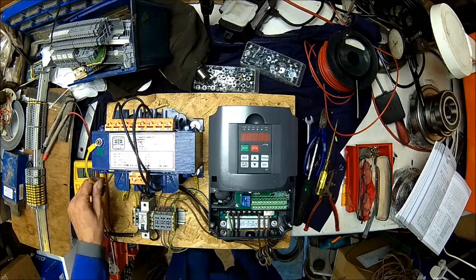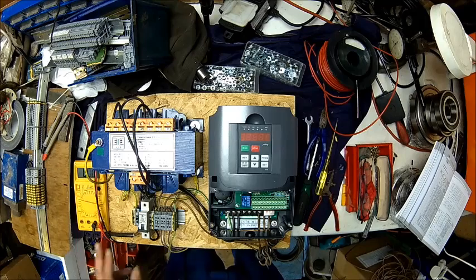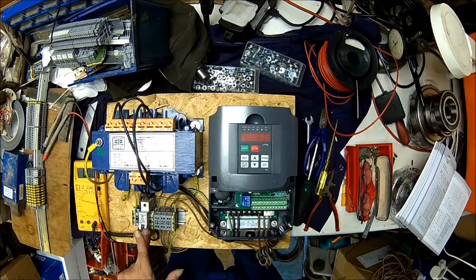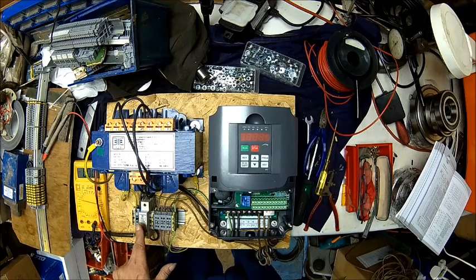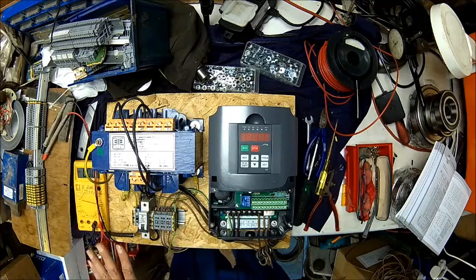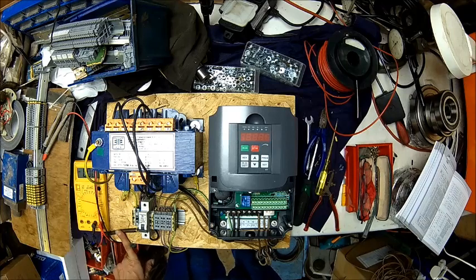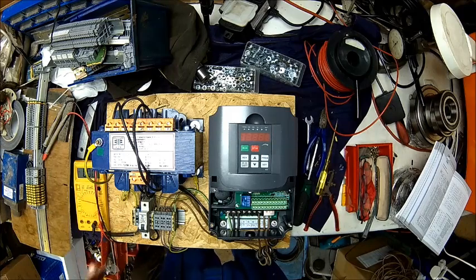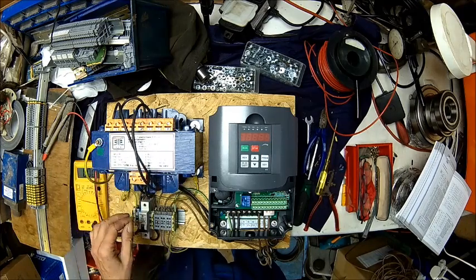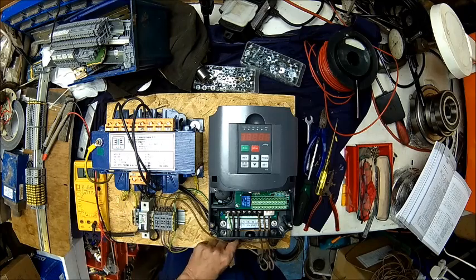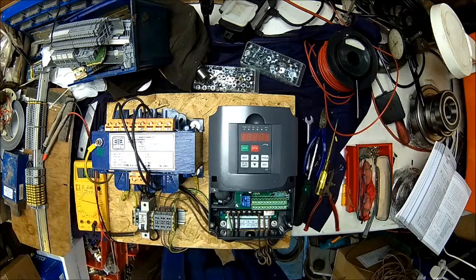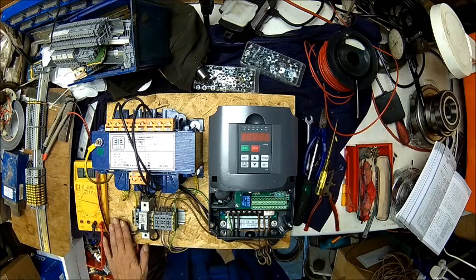Alright, everything is grounded. Inverter is grounded, transformer is grounded. The breaker is the maximum rating of the inverter, plus a little bit of inrush current, 20 amps. That's what the whole set can do. But it's going to have an external fuse, whatever the rating is of his supply and his cable. That's what he needs. The cable work is good for 20 amps. This cable work is good for the 9 or 10 amps which comes off the inverter. So this thing is okay so far. The supply is not my business.